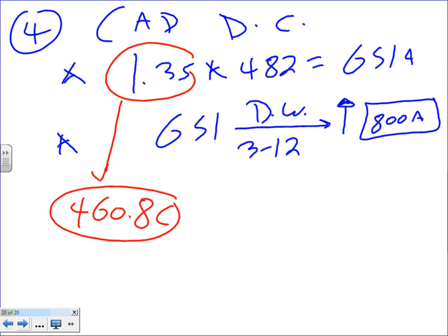If you use 208, all you have to do is multiply the numbers you have here by 1.33. We'll take an example about this one, guys. Again, U-frame is the old, T-frame is the new, and it will give you the size directly, no calculation needed.